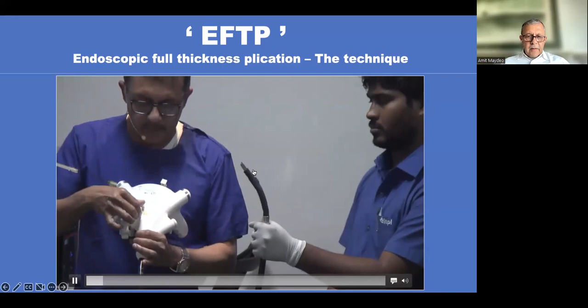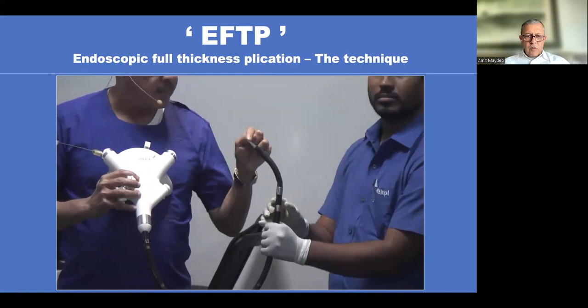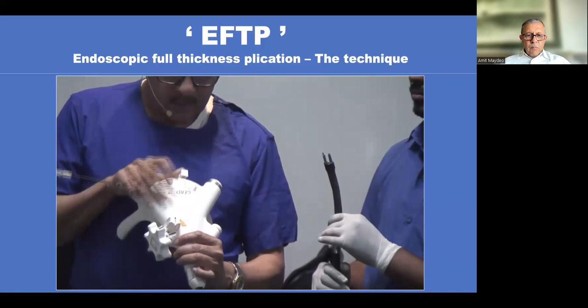And by rotating this handle, there is a 1-to-1 transmission of rotation till the end, and you can go to any part of the OG junction by rotating it. So the first thing I'm doing is showing you how this device can be made into a U-turn by turning this knob. By turning this knob, you can turn the device towards the U. Then I'm going to show you how the arms are opened. To open the two arms, this lever has to be turned. So you push it ahead, and then we move the lever towards one side, towards the right.